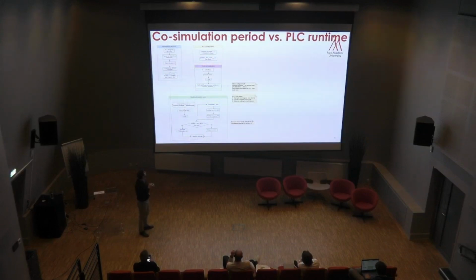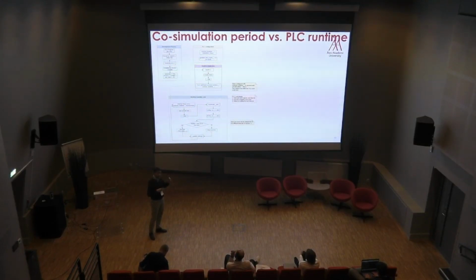What it does basically is that you create the program of the PLC, and when it's translated into a PLC simulator, or into real hardware, it gets a loop, and inside the loop it checks if any input signals are available. It does the computation and provides the output, and then sleeps, and then it waits for the next interrupt tick to do the same thing again. And this contrasts a bit with the co-simulation algorithm, because the co-simulation algorithm has its own time step and tries to involve the PLC program in doing something, while the PLC has its own runtime. This is the runtime loop that the PLC logic follows.